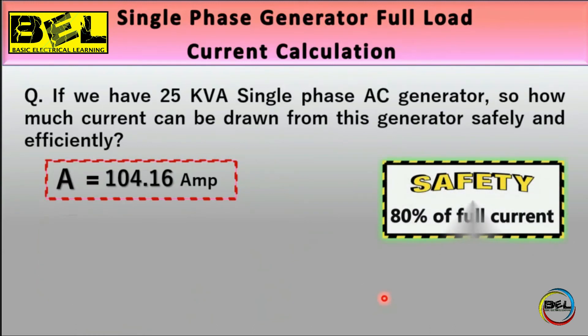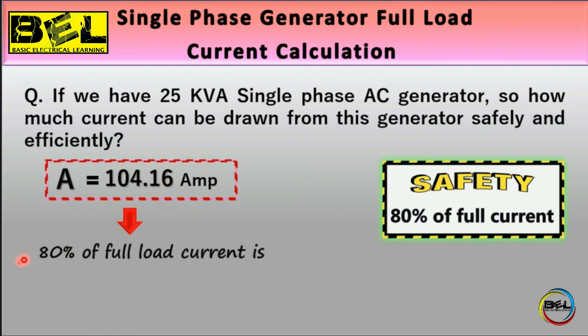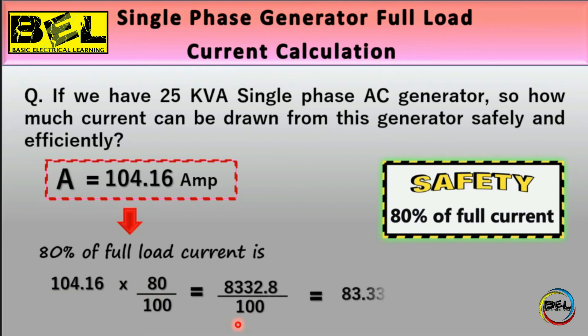For generator safety, we take 80% of the full load current. A link explaining power factor in detail is also available. The calculation is: 80% of 104.16 A = 104.16 × 80 / 100. Solving this gives 83.33 amperes. That is our safe operating current — if we apply this load level, the generator will work efficiently.